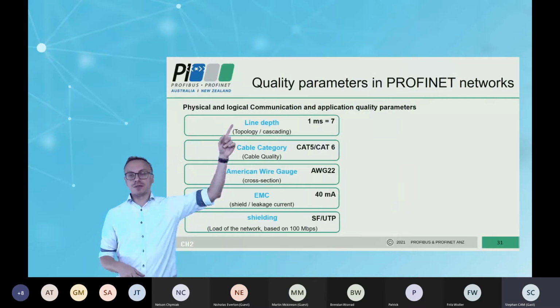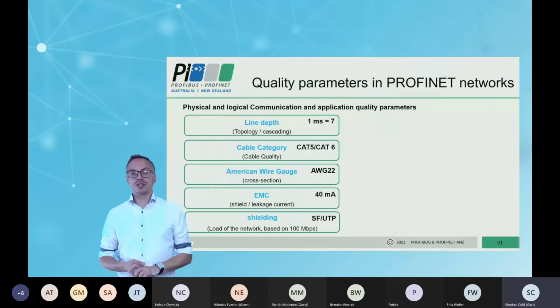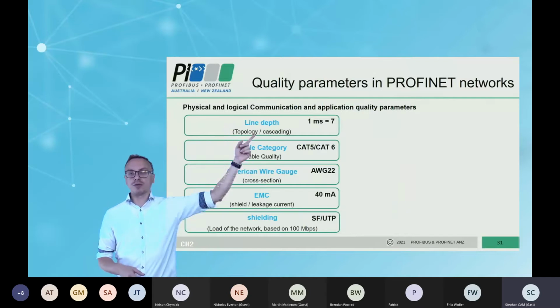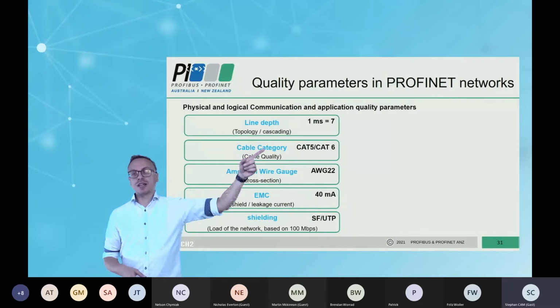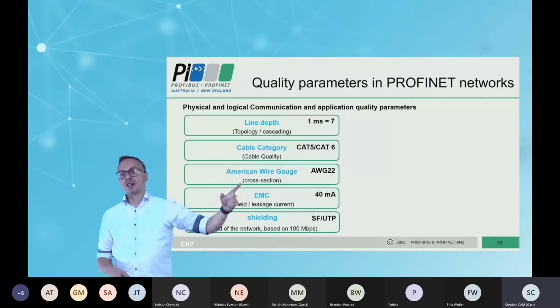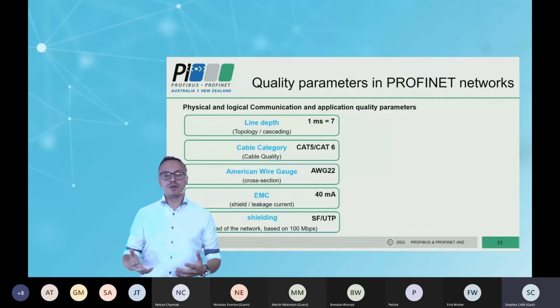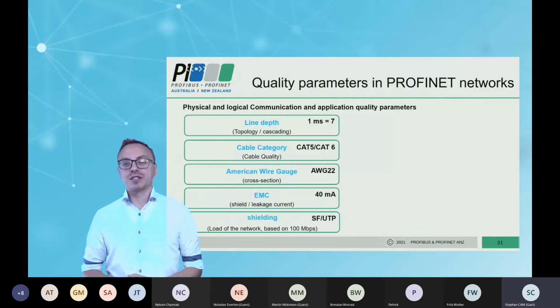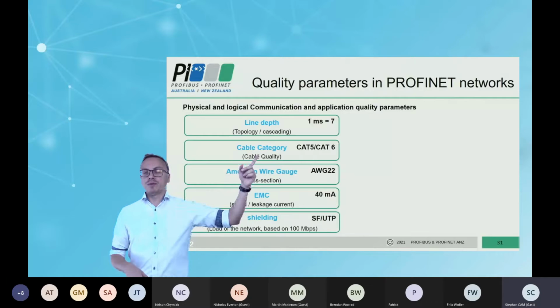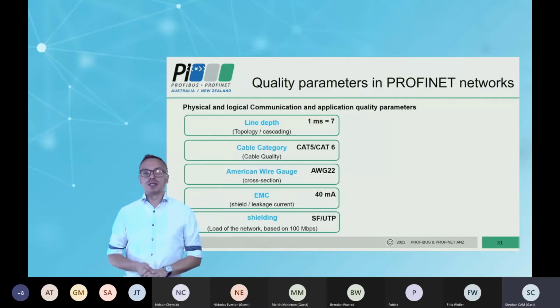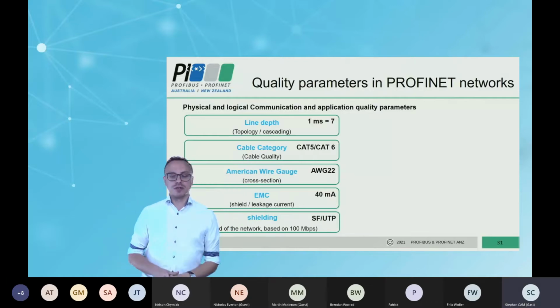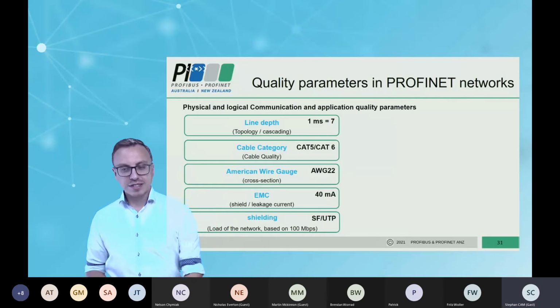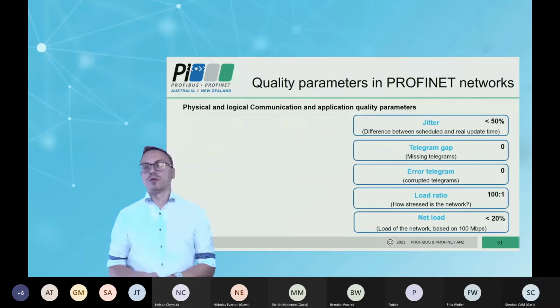So this is how you can find out these values. I say it again: line depth and topology, you can find out with a topology scanner, for example the ProScan Active. Your cable category and your shielding, you can find out with cable certification devices or with a normal cable tester, and your EMC situation you can measure with clamp meters. That makes it easy, and it's very easy to do by your own.